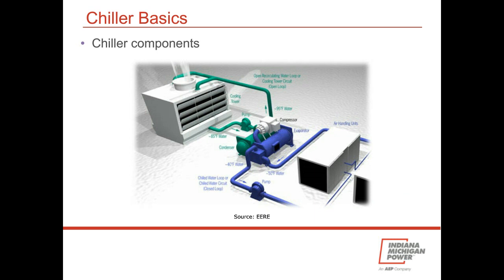All right, we've talked about the rooftop units. Turn our attention to chiller components, chiller operation. Here you see quite a bit of the hardware associated with chillers. You've got the compressor, with the compressor motor. You've actually got 3 loops represented here. You have a refrigerant loop that's going between the 2 barrels there, the evaporator and condenser barrel, which are filled with refrigerant. And you have 2 water loops that pass through each of those as well.